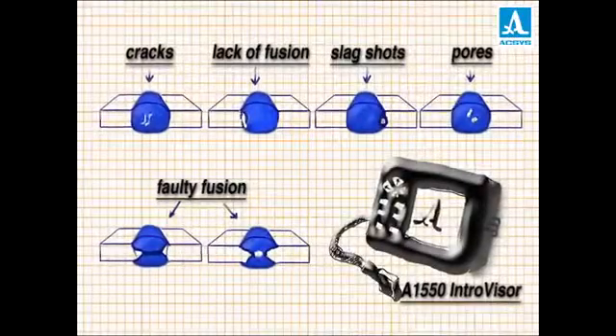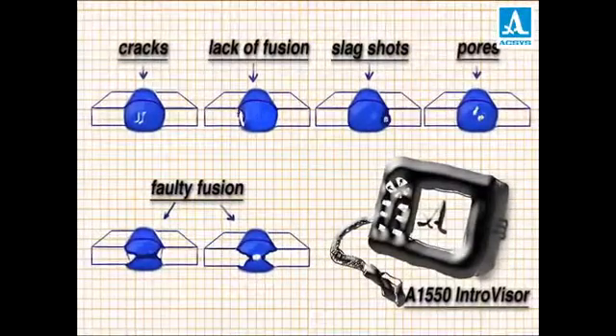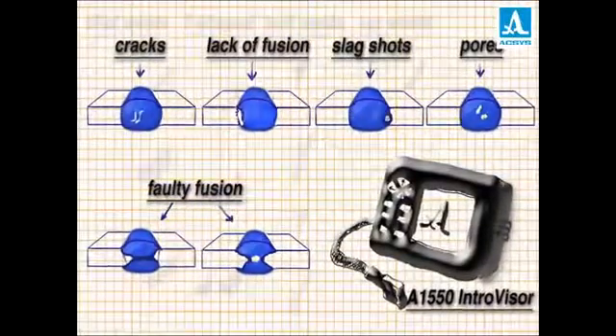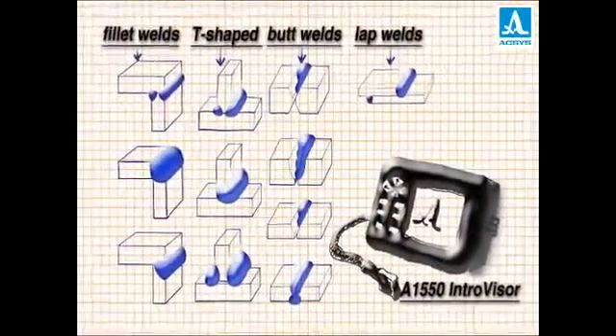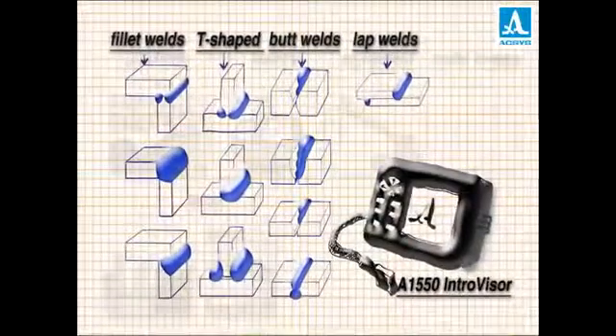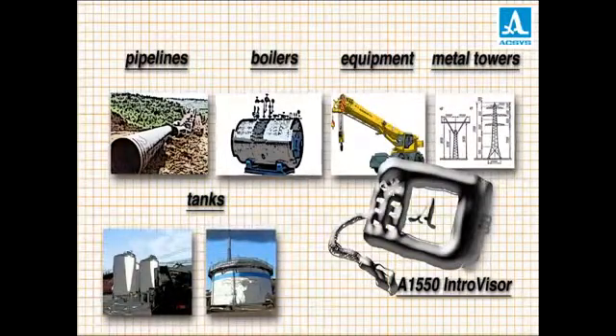With the IntroVisor, it's easy to detect lack of fusion, cracks, slag shots and other flaws in welding joints. It's effective equally for butt, fillet, T-shaped and lap welds. The IntroVisor is used successfully to inspect pipelines of various sizes and purposes, boilers, tanks, metal towers, reinforcing cages, heavy industrial equipment and many other objects.